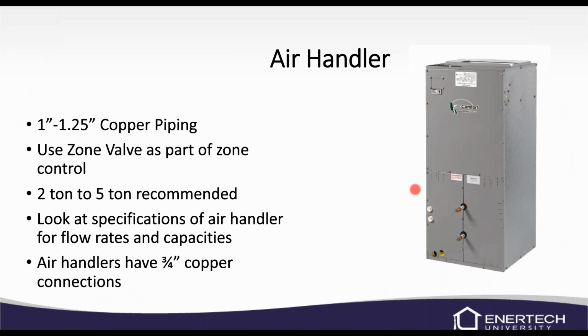Air handlers, right now we're using the Mortex MPH air handler here to the right. It's got 3/4 inch connections stubbed out, but we would recommend running at least 1 inch, if not 1.25 inches, to the unit itself. Definitely use that zone valve as part of the application. We recommend that all air handlers are at least 2 tons and no larger than 5 tons.